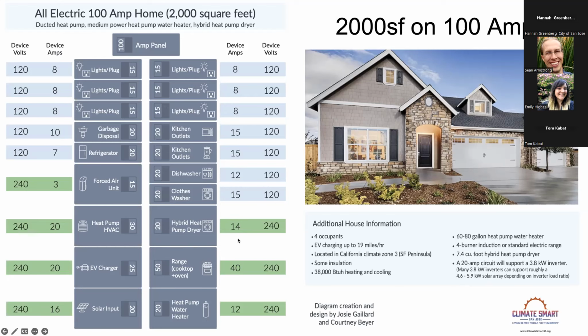Keep in mind these things also get multiplied by 0.4, the coincidence factor. So they don't actually show as their full amperage on your service, because the assumption is, according to code, they're only on about 40% of the time. So they get derated by the coincidence factor, showing only 40% of the values you see here.